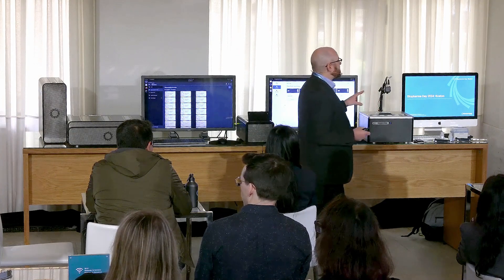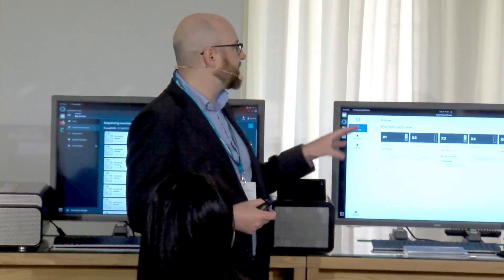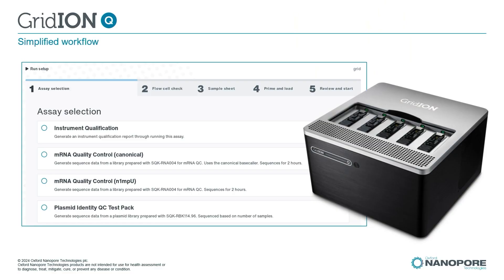We've really worked on simplifying the workflow. The software on the device is very different to our research devices. Our research-use MinKNOW software has all the settings you would need to run any experiment, whereas our GridION software has very locked-down assays with all the right optimized conditions for each experiment — things like sequencing time. For mRNA, we only need two hours of sequencing. It's not a human genome; we don't need days. So we can go from sample to answer in a single day for mRNA.